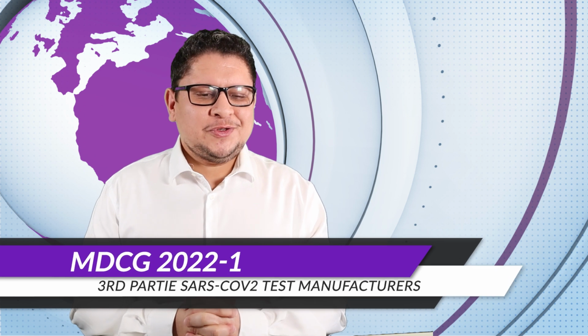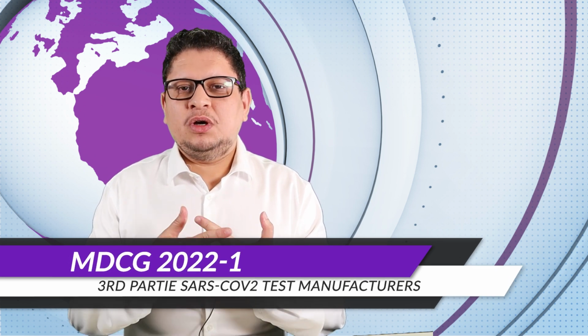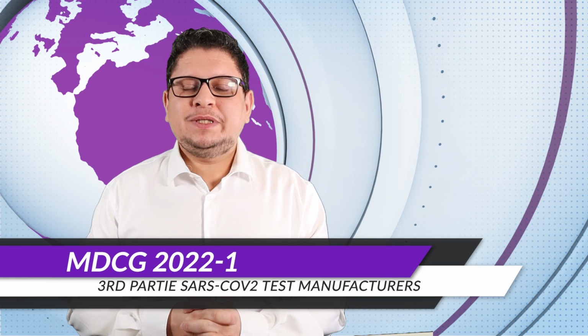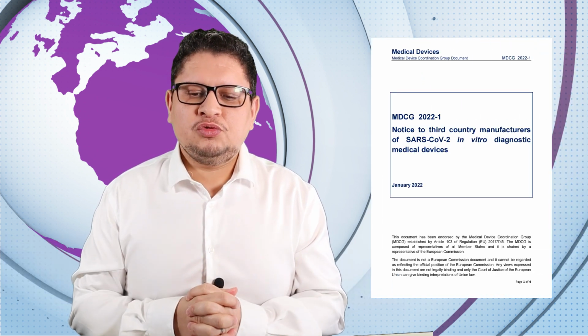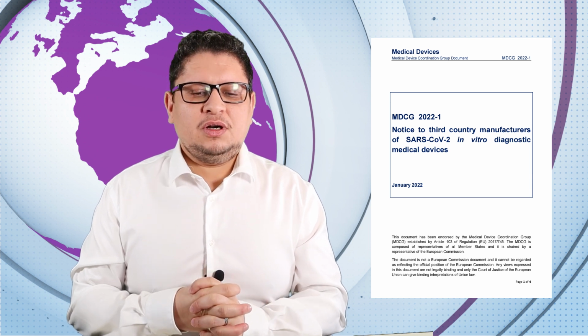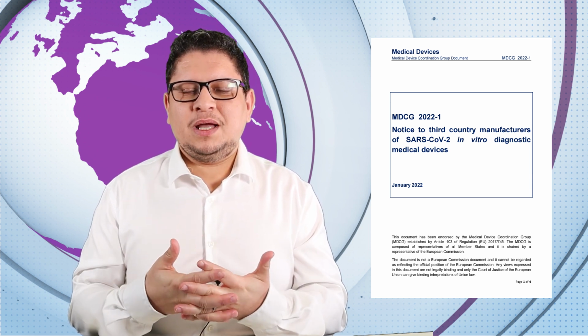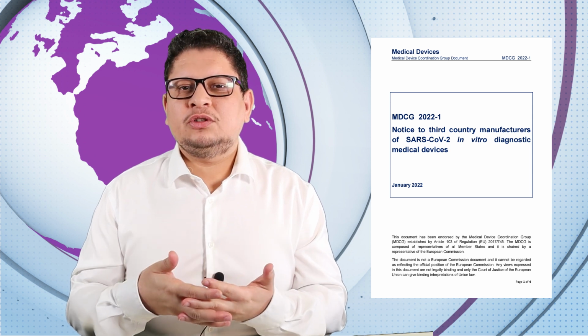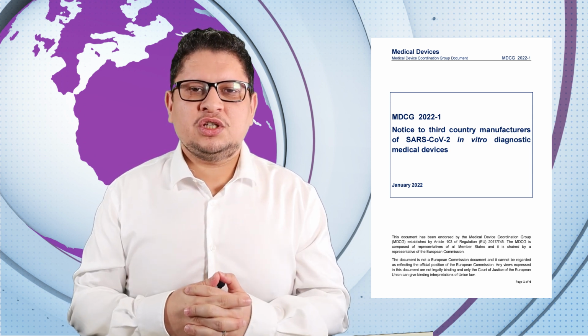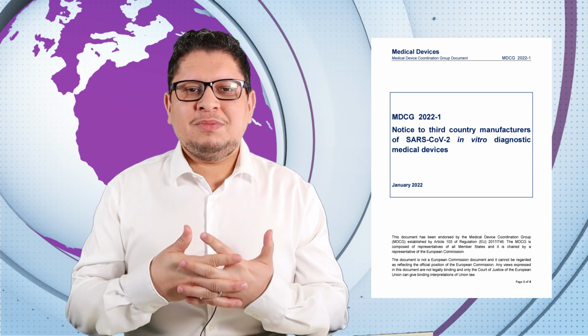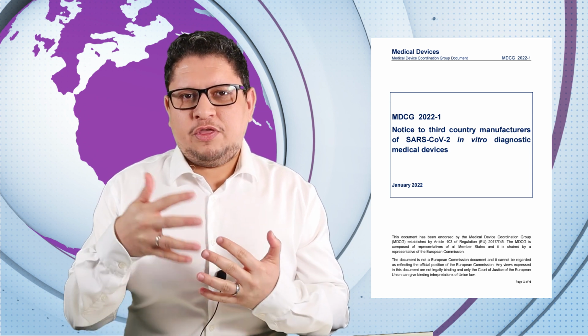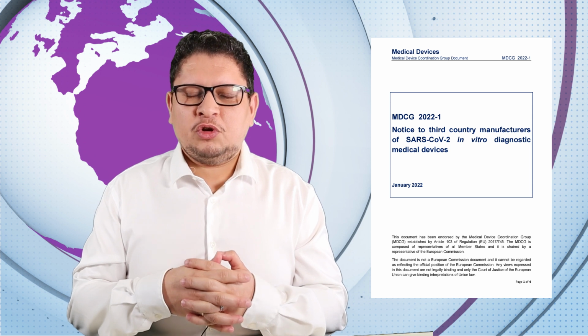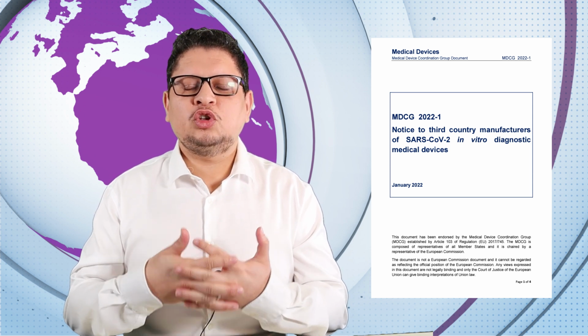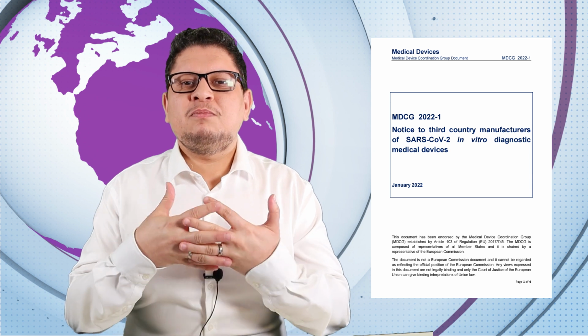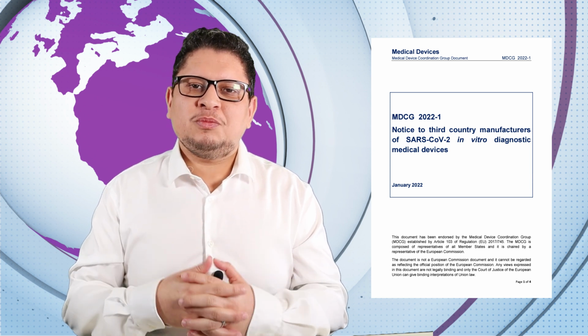Okay, guidance is next. We have the MDCG 2022-1 guidance, which is a notice to third-country manufacturers of SARS-CoV-2 in vitro medical devices. This document is like a reminder, like what we saw before from the Finnish organization FIMEA, for third-country manufacturers, so manufacturers that are not located in the European Union, explaining the most common issues that were discovered about those products.